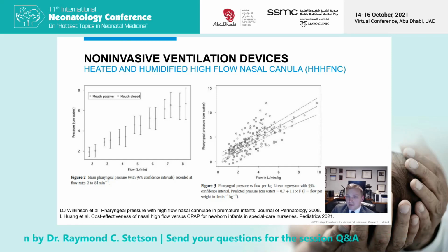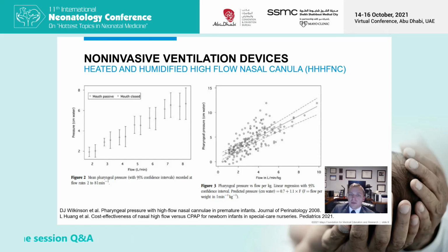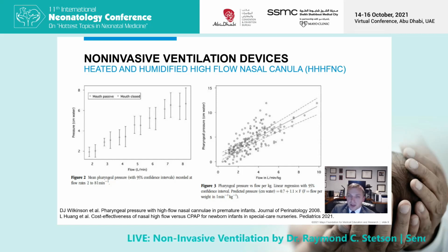High-flow nasal cannula systems have fluctuating airway pressure, and all systems require a pressure pop-off valve for patient safety. When the cannula are occluded, very high airway pressures can be recorded if the pressure pop-off valve is not in place. Wilkinson et al. described an equation to estimate pharyngeal pressures based on high-flow nasal cannula flow rates and patient weights. They also described similar airway pressure measurements for patients treated with high-flow nasal cannula when their mouths were open versus when they were closed.